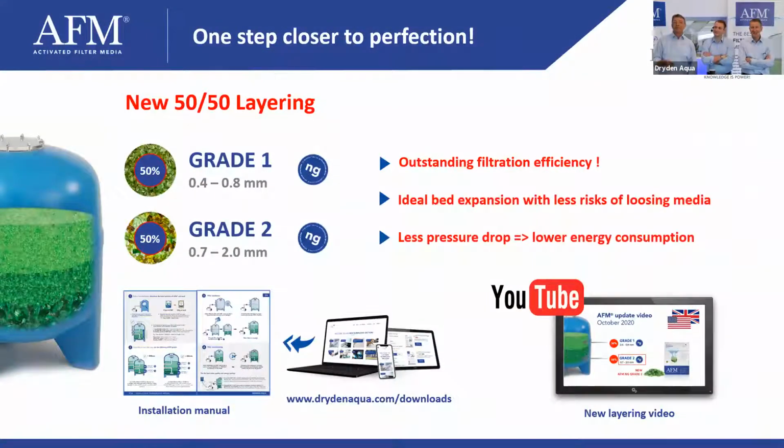Remember first for the layering, it's really the 50-50. Why? Because we changed the grading, remember, from 0.4 to 1 to 0.4 to 0.8. So we made it smaller, more narrow. Grade 2 is now, with the NG activation, really a hybrid. It's support and filtering in both. It's filtering better than sand, just the grade 2.